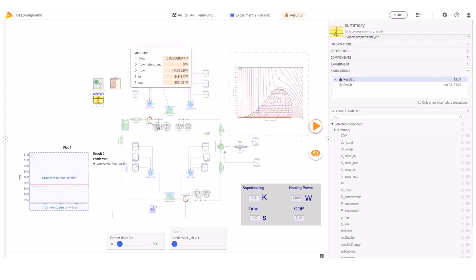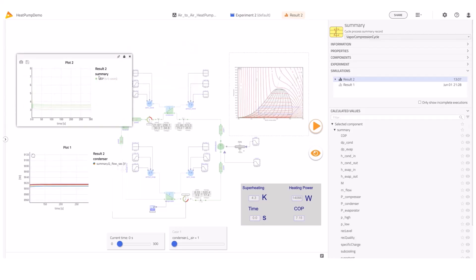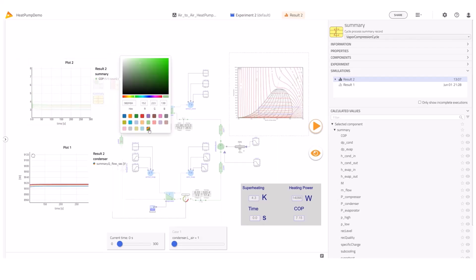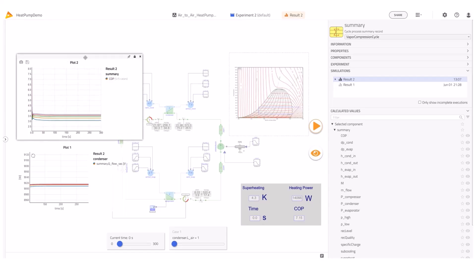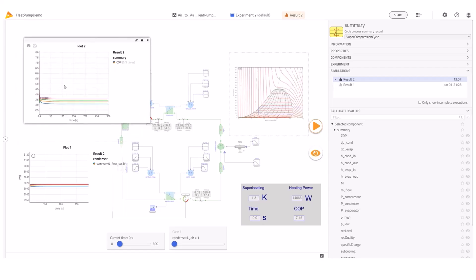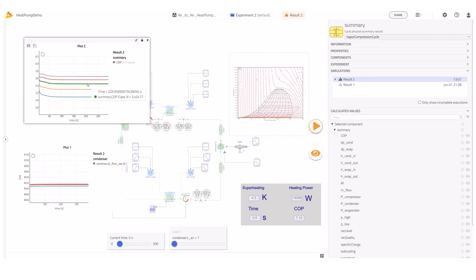Two main things are interesting. First, the heat flow doesn't change much with the different areas. But at the smallest heat transfer area, the COP is much lower than in the other cases. This is explained by the compressor working extra to reach higher pressures and temperatures to maintain the heat transfer levels. So in this case we identify an undersized condenser.